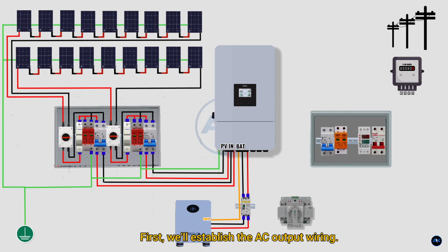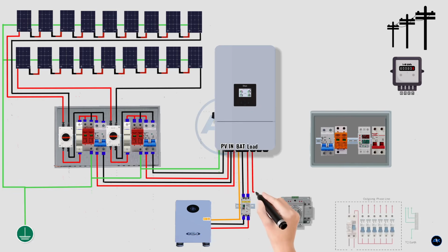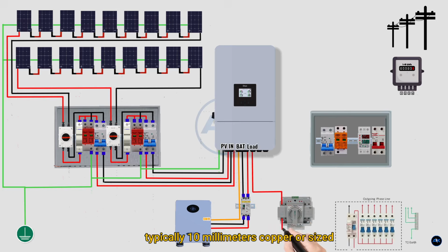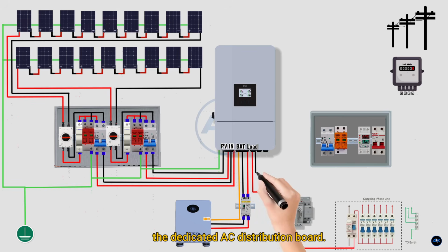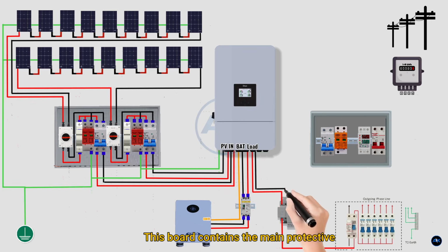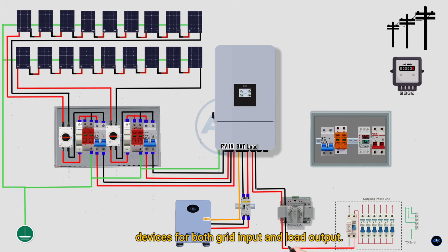First, we'll establish the AC output wiring. Run appropriately sized conductors, typically 10 mm copper or sized according to local code, from the inverter to the dedicated AC distribution board. This board contains the main protective devices for both grid input and load output.